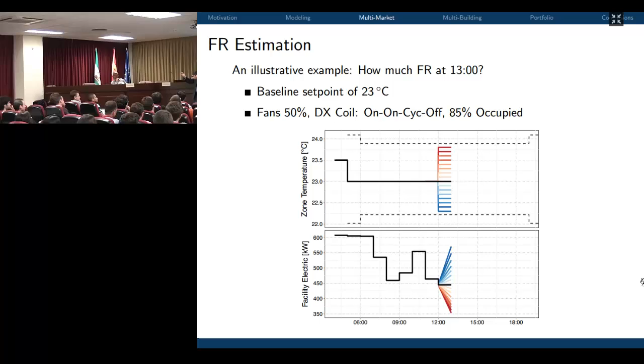So if we have 2 compressors running and a third one cycling, that's this case here, we get this interesting relationship: as we increase the temperature set point, the power consumption goes down, and as we reduce it, it goes up. We might have to call for another compressor, or one compressor less. So this is 2 instead of 3, and here it's 4 instead of 3. This is a situation where you cool the building so the 4th and last compressor needs to run as well. It's simply done by changing set points.